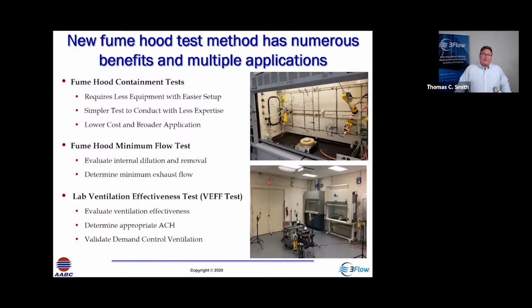So interestingly enough about IPA is that not only can you use it to measure hood containment, you can also use it to put the probes inside the hood and determine how low can you go before you get to a lower explosion limit on the hood. And then we can pull it into the laboratory and look at the air change rates. How effective are the air change rates at minimizing concentrations in the space? We want to make sure that the lab provides secondary containment. We want to make sure that it dilutes and removes contaminants. That's very important now during the COVID.